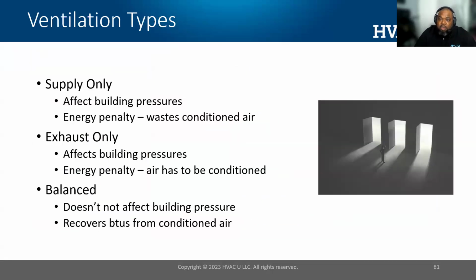All right, ventilation types. You got the supply only, where I'm going to push air into the building. It affects the building pressures. And there's an energy penalty where, as I push 1 CFM of air inside the building, it's going to push 1 CFM out. The energy penalty means that the air that I've paid my utility company to condition is eventually going to get pushed out my building shell, and the air that has come in to replace it is going to have to get reconditioned. All right, so you get ventilation for respiratory health, but you do suffer an energy penalty.